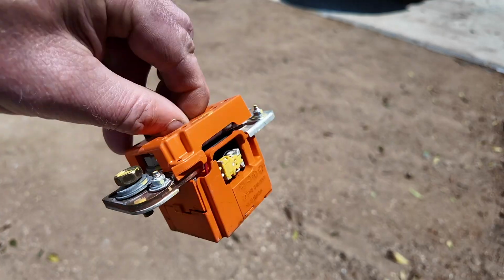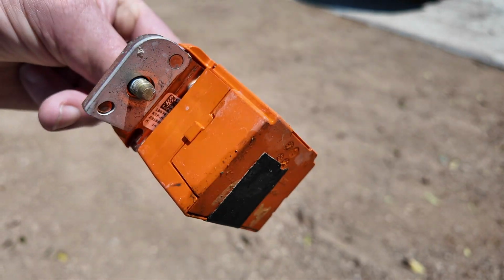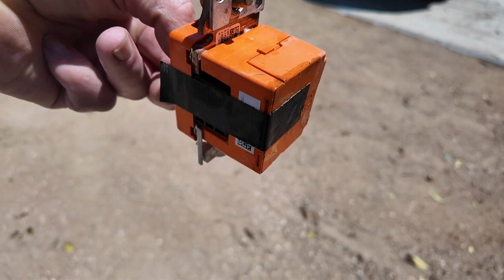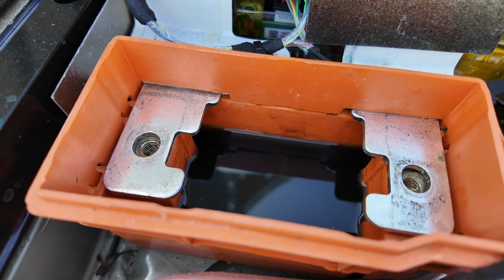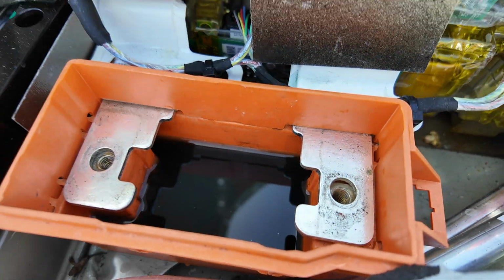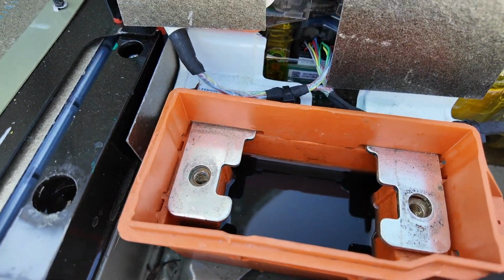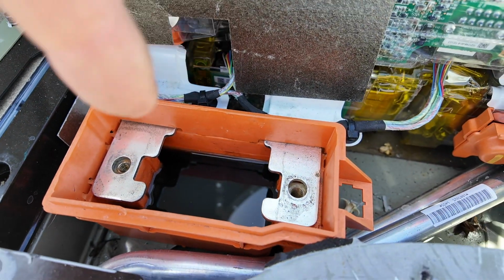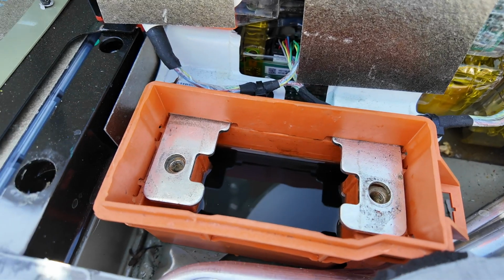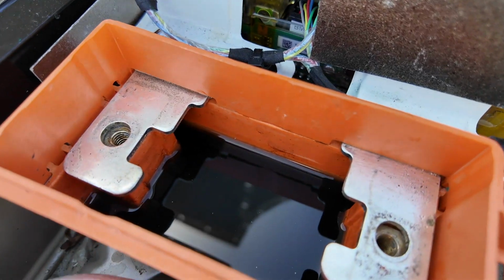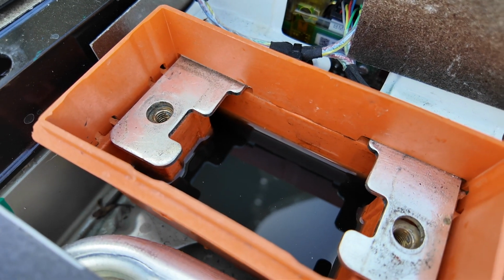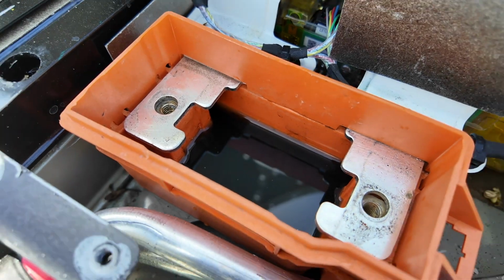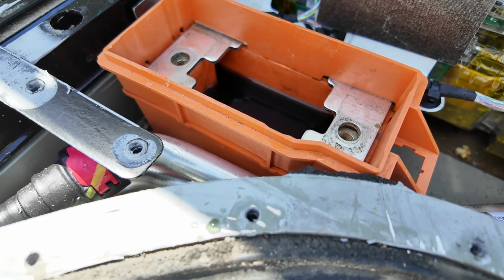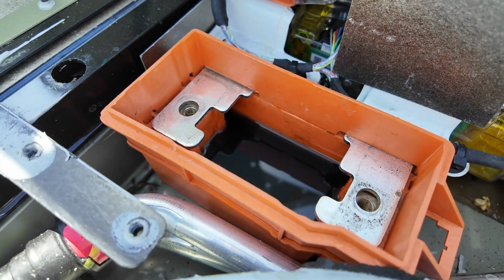Okay, pyro fuse is out, and as expected, soaking wet, full of water. That's a positive indicator. Plus we have water sitting in this tray here, and bolts below submerged in the water. Obviously I don't want to touch this right now, but that is what's causing the contact to ground: water being in contact with the pyro fuse.